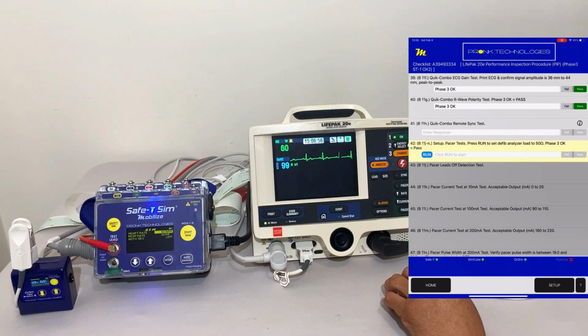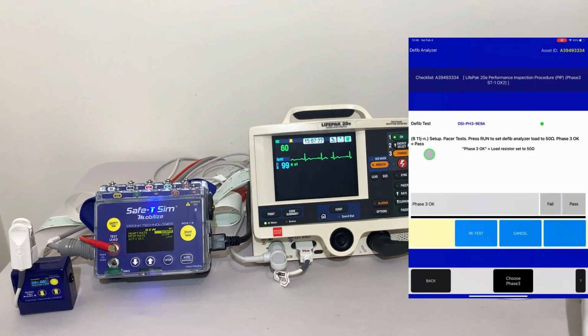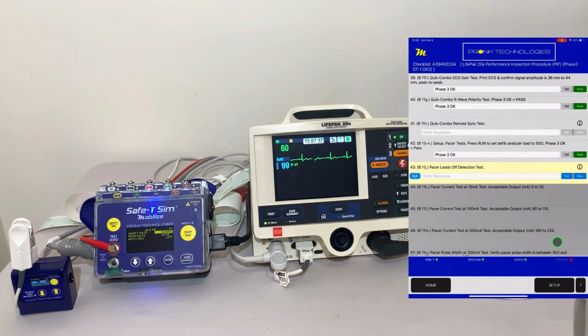The next set of tests we need to run are the pacer tests. The very first thing we need to do before we get started is make sure that we've set the defib analyzer to the right impedance per the manufacturer's requirements. That's important to make sure our measurements are truly within the tolerance that are specified. In the case of the LifePak 20E, we need to set that impedance of the defib analyzer to 50 ohms. So let's go ahead and do that, and we can do that via the app here as well. So the app will communicate to the defib analyzer and instruct it to set its internal impedance for pacer testing to 50 ohms. So we've done that. We've made sure we've got our equipment set up properly. We can go on to the next thing.